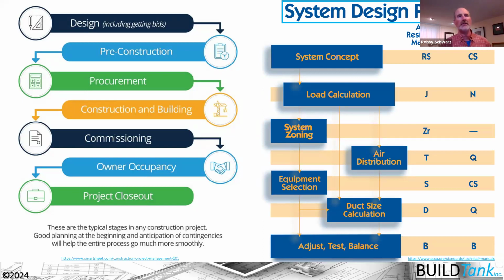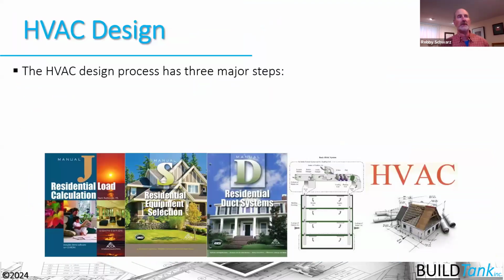But what we need to understand is that this design process for the HVAC system that's going to be installed happens before construction actually occurs. So we're making a number of assumptions about the quality of the building thermal envelope that this system is going to go into. And what I want to point out here is that, again, we need to do that level of inspection or quality control, because if these assumptions aren't actually carried out, if our house isn't as tight as we thought it was, if the insulation is compressed in the cavities and it's not performing at its rated R value, that's going to have a significant impact on the performance of the HVAC system that we're actually going to install in our house.